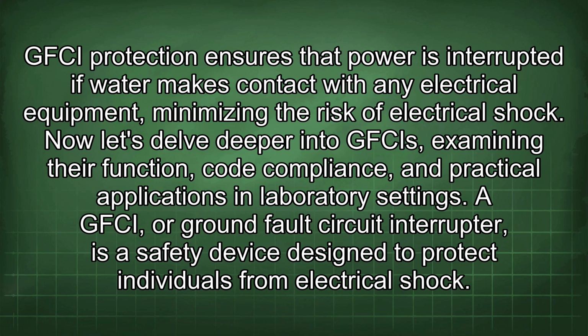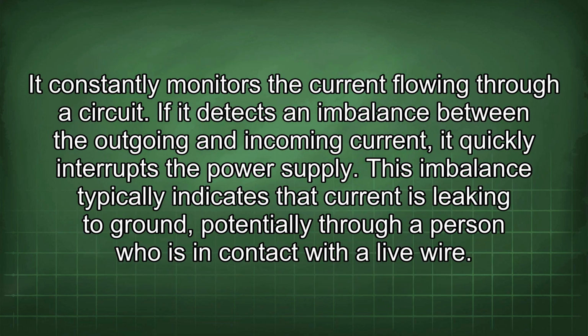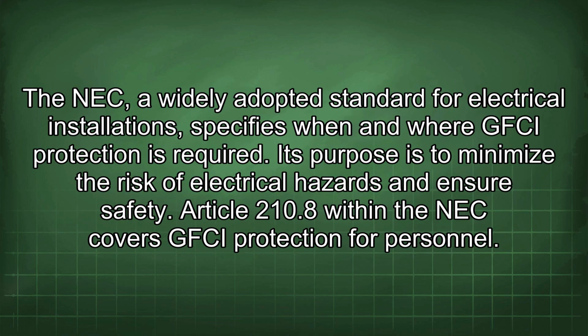A GFCI, or ground fault circuit interrupter, is a safety device designed to protect individuals from electrical shock. It constantly monitors the current flowing through a circuit. If it detects an imbalance between the outgoing and incoming current, it quickly interrupts the power supply. This imbalance typically indicates that current is leaking to ground, potentially through a person who is in contact with a live wire. The NEC, a widely adopted standard for electrical installations, specifies when and where GFCI protection is required. Its purpose is to minimize the risk of electrical hazards and ensure safety.